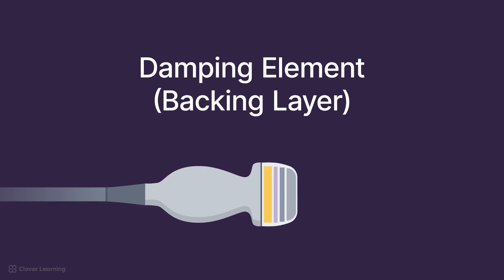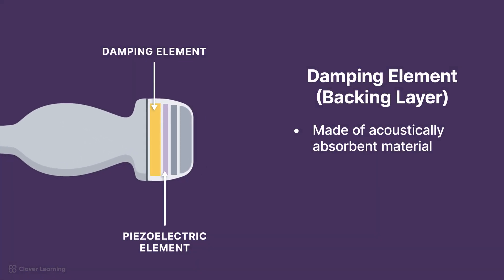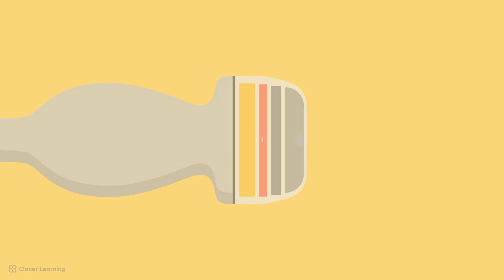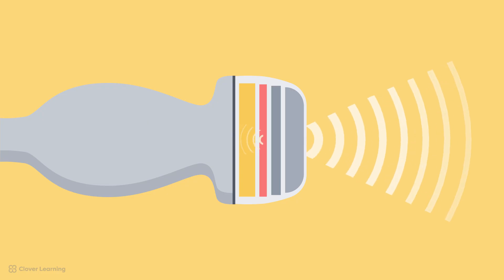Now we will discuss the damping element or backing layer, which is located towards the back of the transducer behind the crystal. It is made of acoustically absorbent material, such as epoxy resin infused with heavy particles like tungsten or lead, or other composites specifically engineered for high acoustic attenuation. Its job is to absorb stray vibrations, preventing echoes from lingering. The damping element works to absorb vibrations that can persist beyond the initial pulse and create what are called ringing effects.